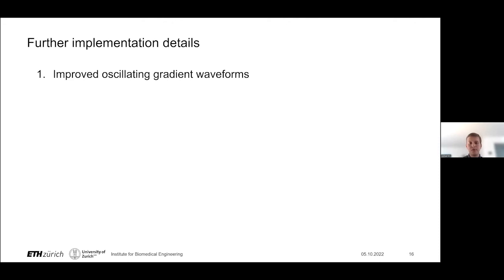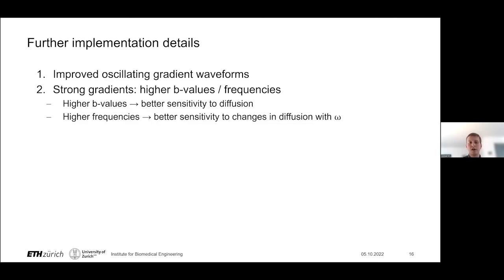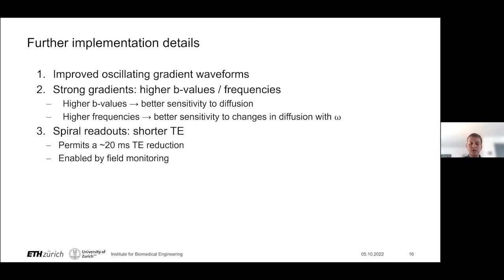In addition to using the improved oscillating gradient shapes, we have used our high-performance gradient system, which allows us to achieve higher b-values and/or higher frequencies. Higher b-values give better sensitivity to diffusion, while higher frequencies give better sensitivity to changes in diffusivity with frequency, because a higher frequency provides a greater difference in diffusivity relative to zero frequency. The final part of our implementation was using spiral readouts, which enabled us to shorten the echo time — particularly enabled by having a field monitoring setup, practically necessary for reconstructing spiral images — allowing a reduction of around 20 milliseconds in echo time.